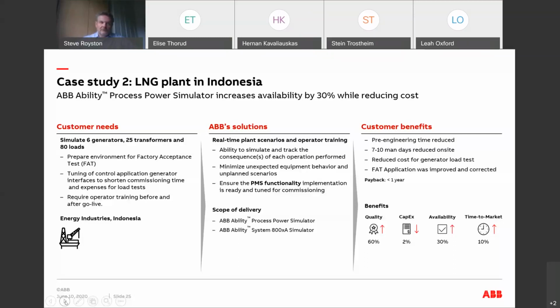load tests for the generator, and we are always the last people to participate in these types of tests. Especially load shedding tests are almost impossible to do on a live plant, and even during commissioning they have limited purpose. Even if you test something, you will only get the answer when the first disturbance is there. Now we can utilize the simulator to perform all those actions and see the response on the frequency, voltage, and the important parameters. So we can move on to next, Steve.